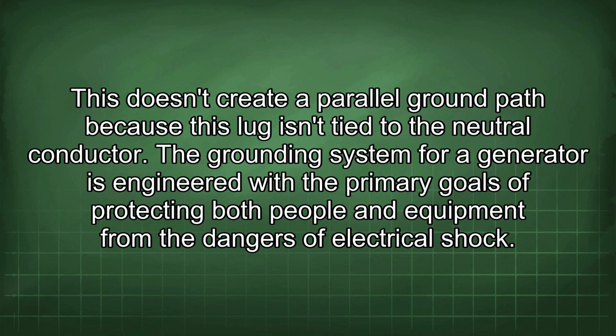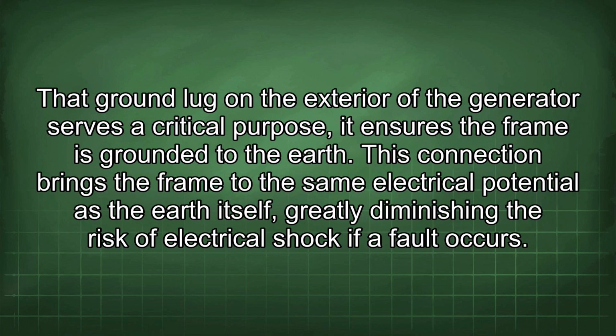The grounding system for a generator is engineered with primary goals of protecting both people and equipment from the dangers of electrical shock. That ground lug on the exterior of the generator serves a critical purpose. It ensures the frame is grounded to the earth. This connection brings the frame to the same electrical potential as the earth itself, greatly diminishing the risk of electrical shock if a fault occurs.